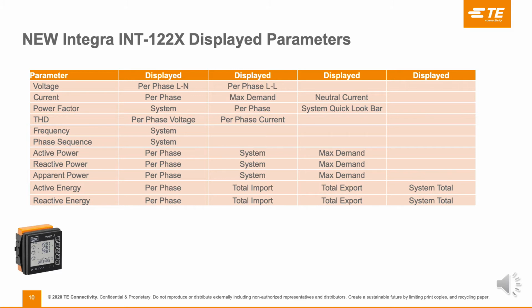Onto the power readings, you've got active power, which is the kilowatts per phase system and maximum demand, reactive, which is the kVAr, which is per phase system and maximum demand, and also the apparent, which is the VA, again per phase system and maximum demand. Onto the kilowatt hour, kilovar hour, which is the active and reactive energy, also states per phase for any active and reactive, total import, total export as a separate reading, and also we'll do the system, so that it'll take away the export and the import and give you total system readings for active and reactive energy.